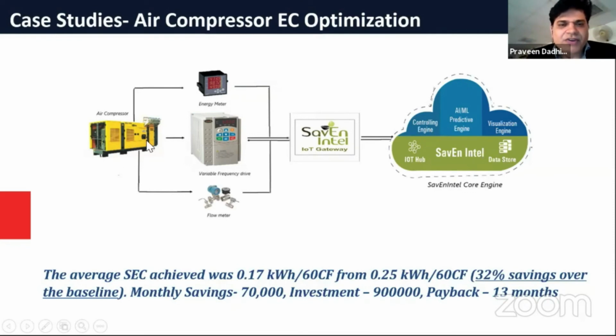The compressor was without VFD. So we went in and digitized the compressor first — installed an energy meter, flow meters, and pressure sensor. We got data for 2 months, every minute, 24 hours. It was a large volume of data, extracted by our IoT gateway.